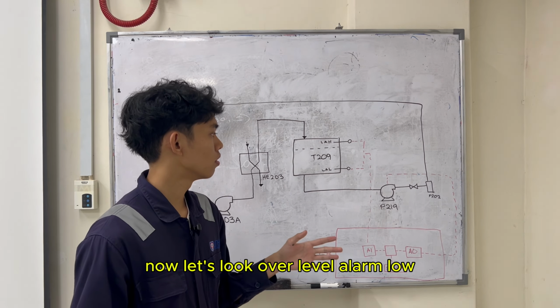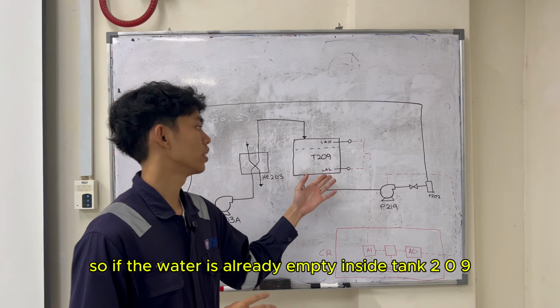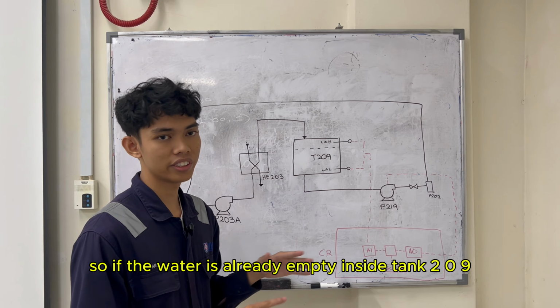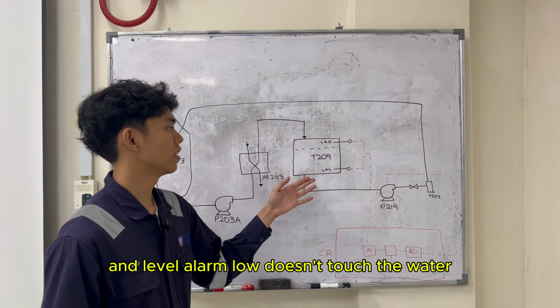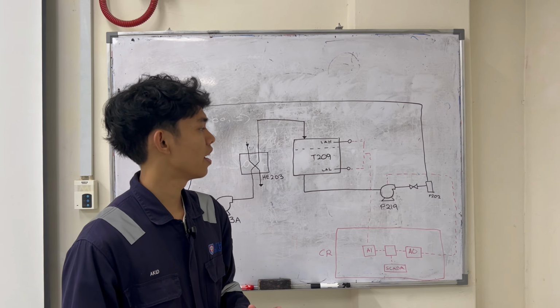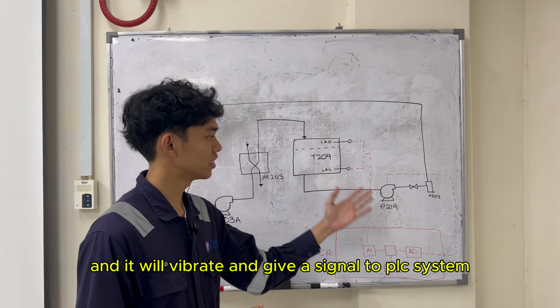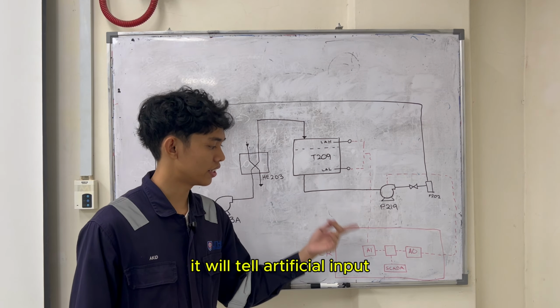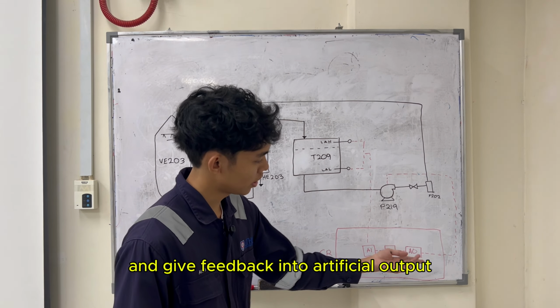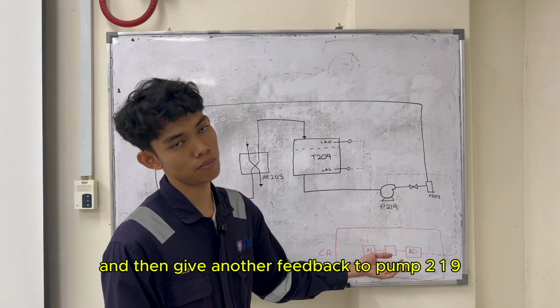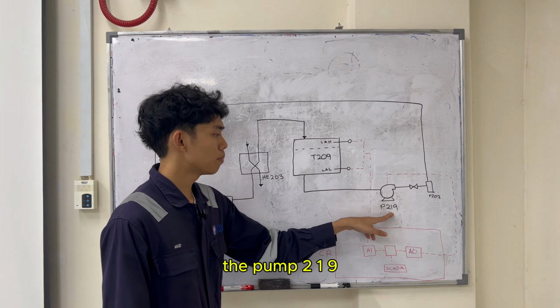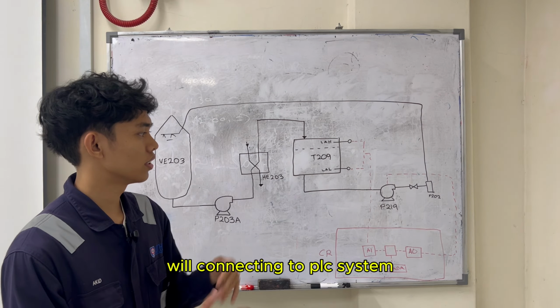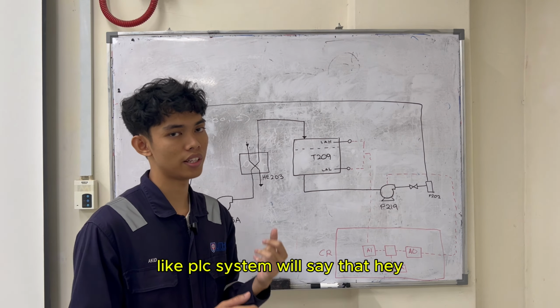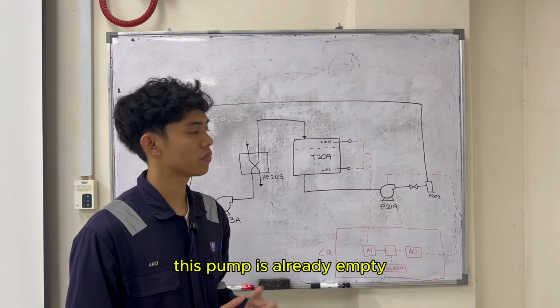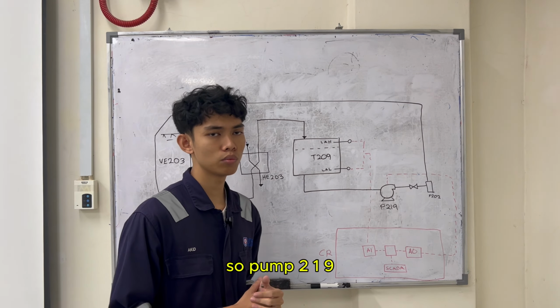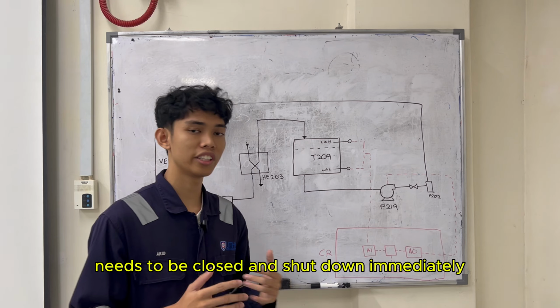Now let's look at level alarm low. So if the water is already empty inside tank 209 and level alarm low doesn't touch the water, it will vibrate and give a signal to the PLC system. It will tell the analog input and give feedback into the analog output, and then give another feedback to pump 219. The PLC system will say, hey, this tank is already empty, so pump 219 needs to be closed and shut down immediately.